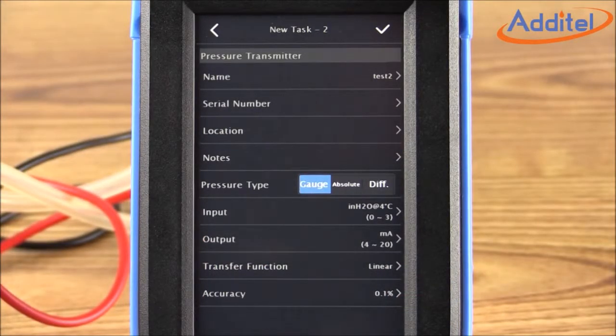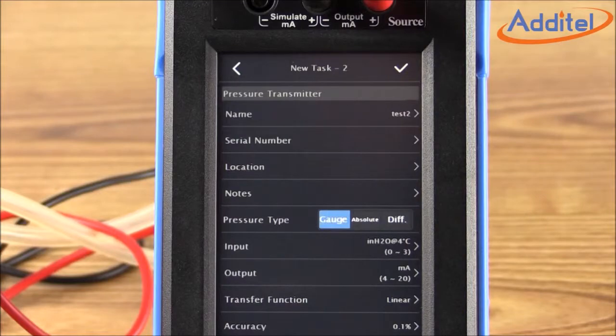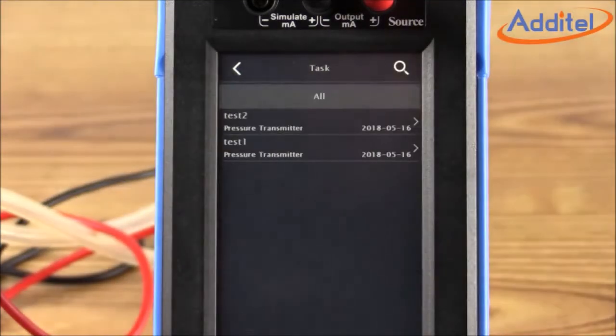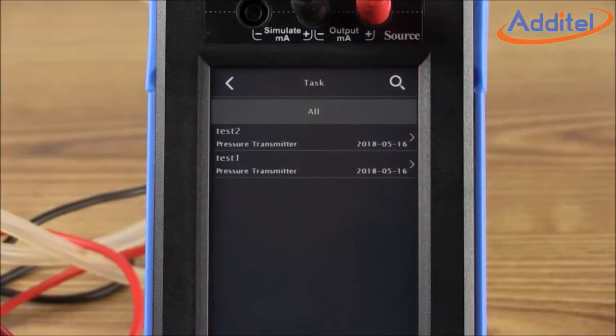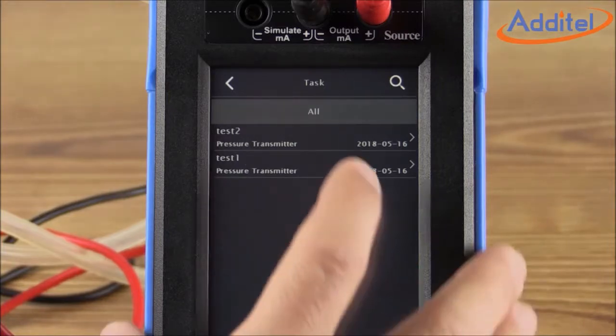From this menu, we can add a number of things identifying this particular test, such as a name, the serial number of our transmitter, a location, and so on. You'll also note some information about the transmitter, such as input, output, and accuracy near the bottom of the screen. When the task information is complete, select the check mark icon at the top right. This will return the calibrator to a list of stored tasks. You may recall that we called our test Test 2, so we'll select Test 2 from the list.